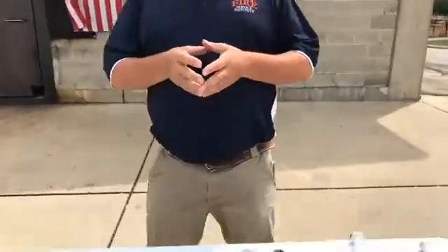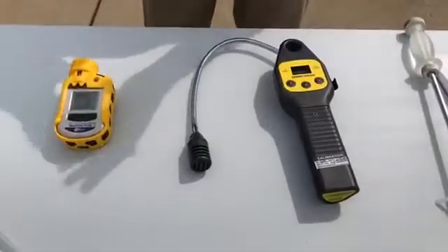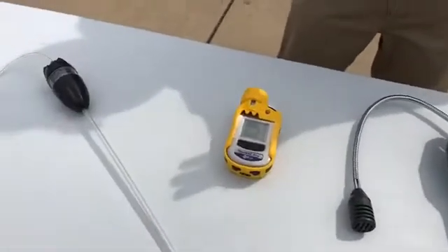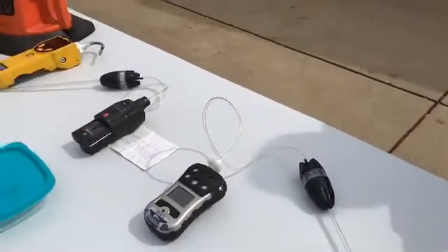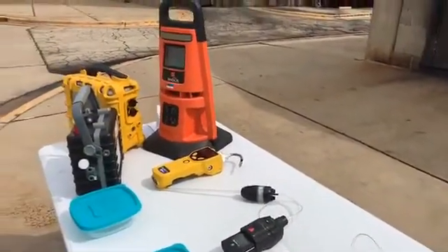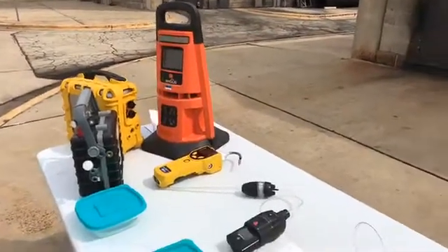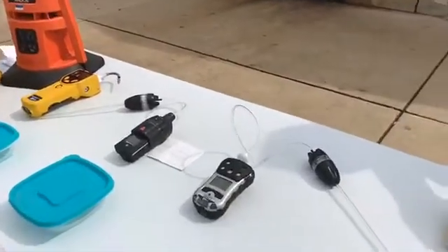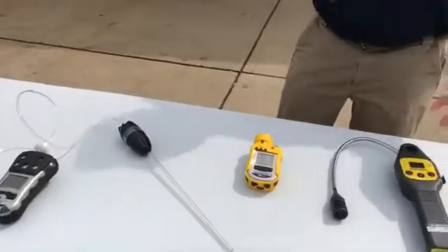The other thing you want to think about within your electronic instrumentation is both the bump testing process and the calibration process. Bump testing should be done every time the unit is going to be used in a real situation. What's a bump test? I put calibration gas to the instrument, or a bump test gas, and I see the sensors react. Once I see that I'm getting reaction out of all of the sensors, I know that my instrument's ready to go. Okay, it's successfully passed a bump. Only takes a few seconds, and it's mandatory for the instrument to see if it's operational. It shows you that that monitor is ready to go to work.